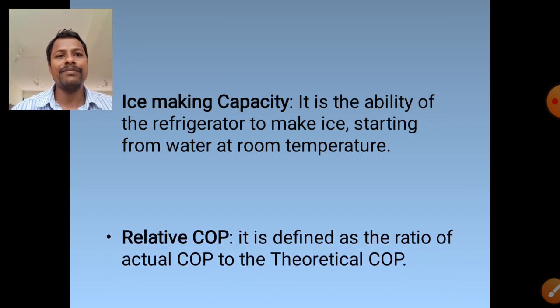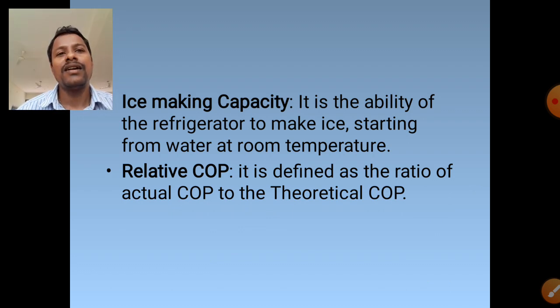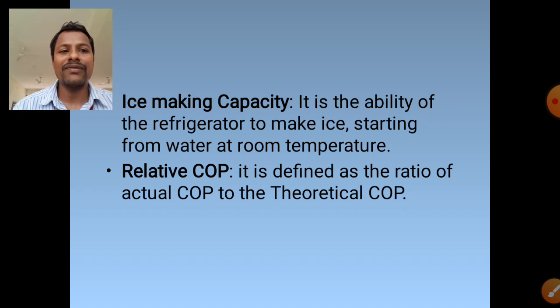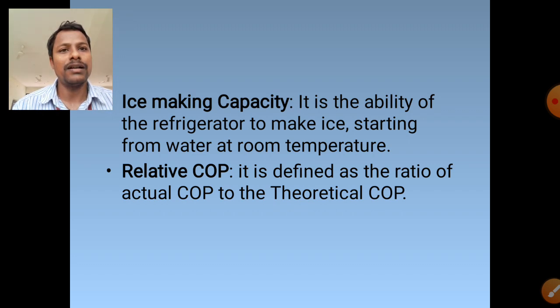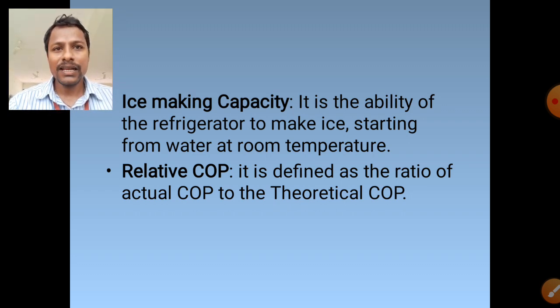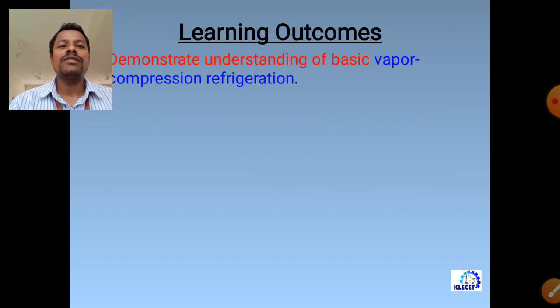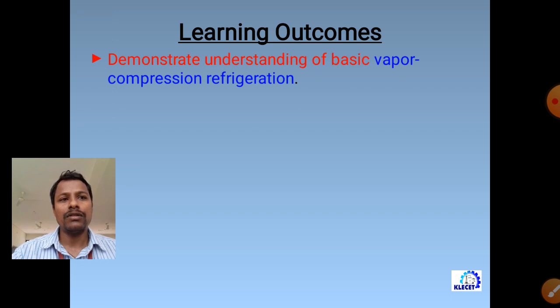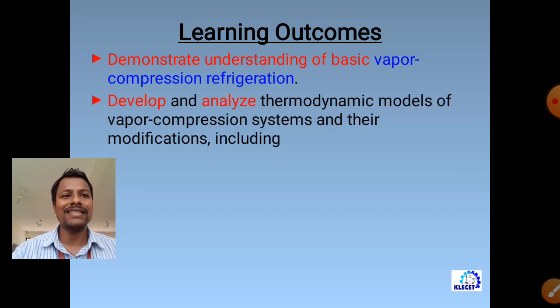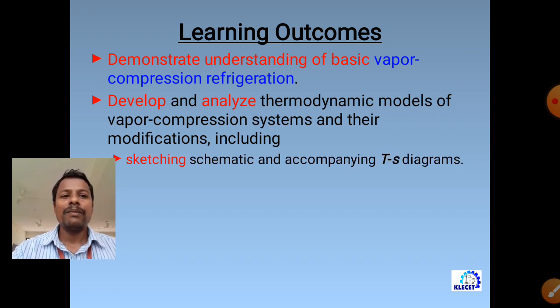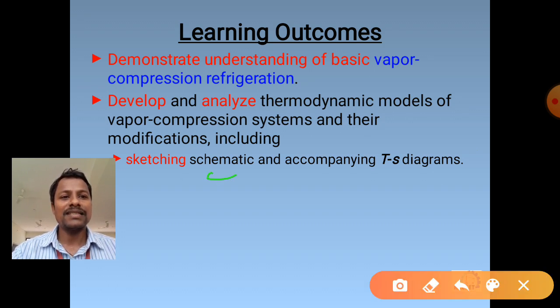The vaporized refrigerant at state 1 enters the compressor, which compresses the refrigerant vapor to higher pressure and makes it move through the circuit. As it is compressed, its temperature increases. The compressor receives work input. Then the refrigerant, after absorbing heat and receiving work from the compressor, comes into the condenser, where it rejects heat energy into the atmosphere, coming out at state 3 at very high pressure.